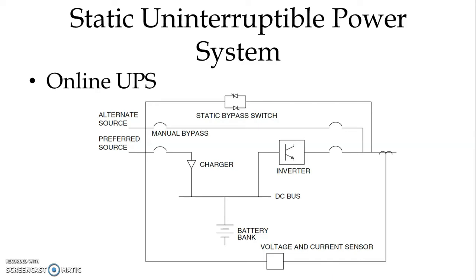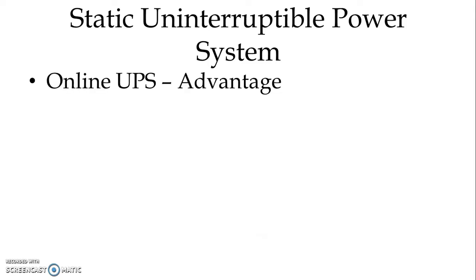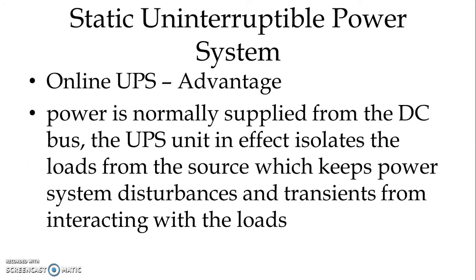So in case of online UPS system, the main advantage is during loss of normal power, there is no actual switching, and continuity of the power to the critical load remains as it is. Now let us see certain advantages of online UPS. Power is normally supplied from the DC bus. The UPS unit in effect isolates the load from the source, which keeps power system disturbances and transients from interacting with the load. So this is one of the main advantages, because our normal power source and load are isolated.